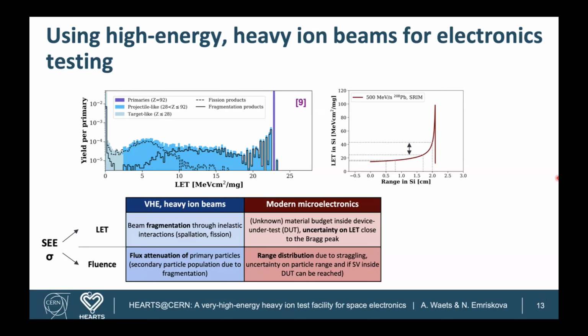The sensitive volume is located at a specific spot, at a specific depth, under a certain amount of material, and it becomes increasingly difficult, certainly when you're operating close to the Bragg peak. So when you're wanting to test at very high LETs, there you get a high uncertainty. You can see it on the figure on the top right. Basically, when you are crossing 300 microns of silicon and you're doing this at a low LET, you are still at the leftmost side of the Bragg peak, let's say.